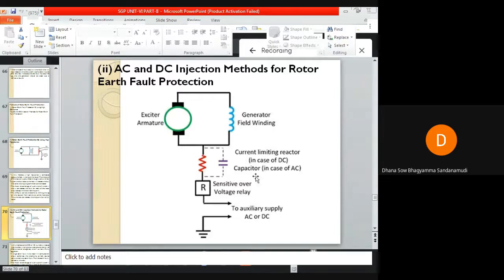There will be leakage of current through the capacitor whenever I am using an AC source. This current will unbalance the magnetic field and increase the stress in the magnetic bearings of the rotor. Another disadvantage of using the AC supply is that the relay cannot pick up the current that normally flows through the capacitance to the ground. Also, if I am using an AC supply, much more care should be taken to avoid resonance between the capacitance and the relay inductance. So in order to overcome all these drawbacks, instead of using an AC supply, you can use a DC supply here.